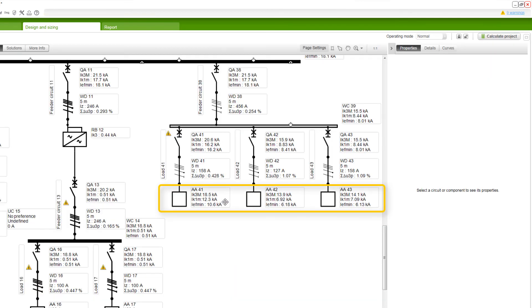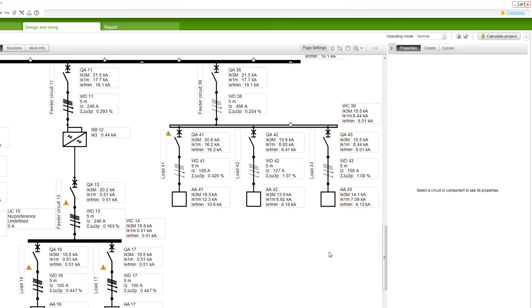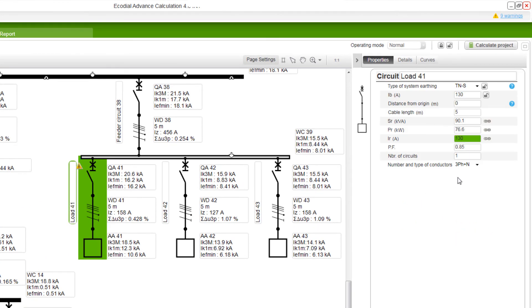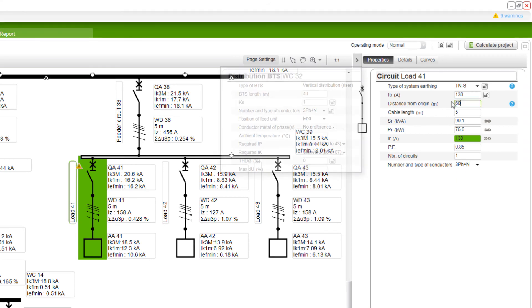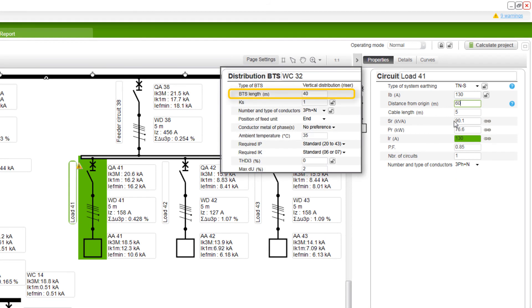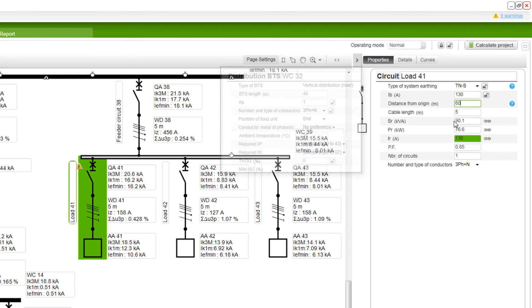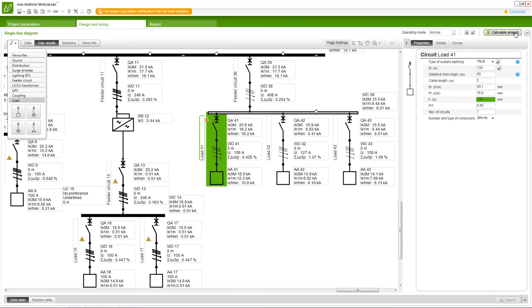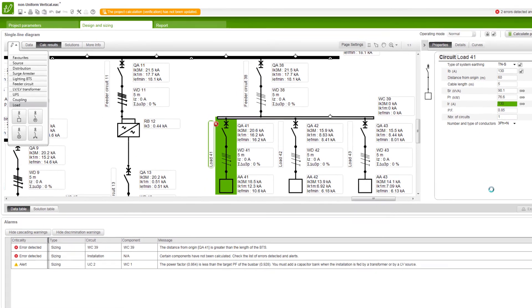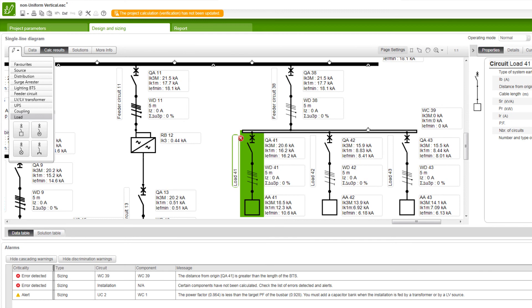After calculation, for a non-uniform busway, the short circuit currents and voltage drops are calculated for each feeder. If the distance from origin of a feeder is more than the length of the BTS, then the network calculation will show an error. You can view the details in the alarm window.